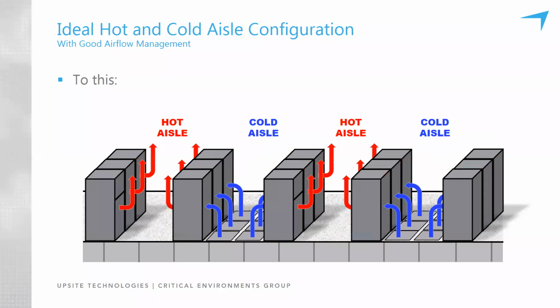We see now in this image that everything is as it should be. There is no exhaust recirculation. The amount of conditioned air being delivered to the cold aisle equals the amount of conditioned air required by the IT equipment.